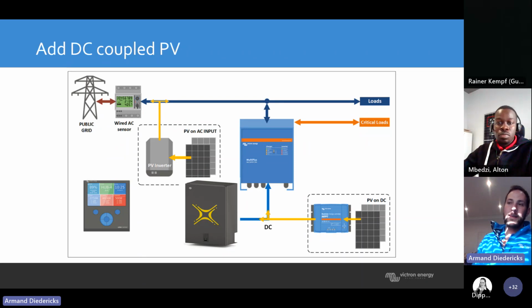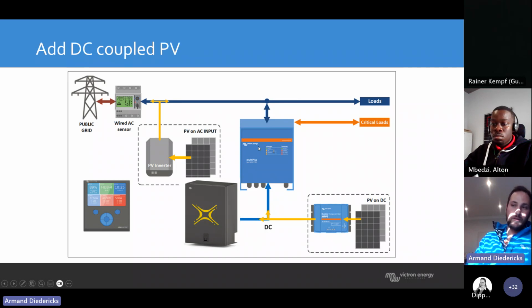So if you do have an 8 kVA unit, just ensure that your PV inverter connected to the output does not produce 8 kilowatt and damage the transformer on the side. It's really unlikely that it will happen. If there's a communication failure between the two units, obviously your GX will be the brain. So if there's a communication failure and it starts exporting more power, then it will damage your inverter. But if you've got 6 kilowatt connected onto the 8 kilowatt on the output, you won't have a problem at all.